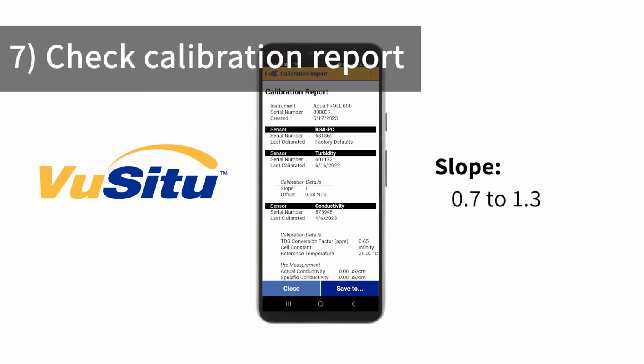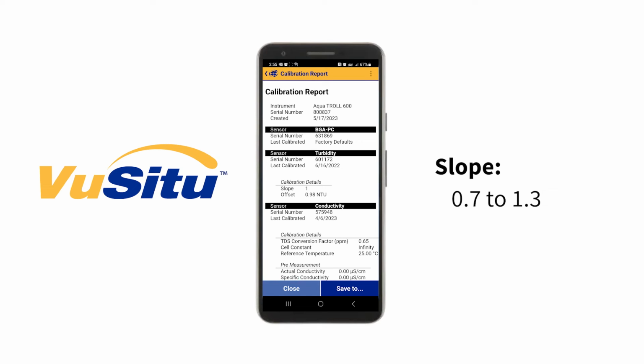If the slope is out of range, there's a few things you can try. First, clean the sensor, then try the calibration again. If the error persists, check for bubbles in the solution and ensure that the end of the restrictor is covered from ambient light. Verify that your calibration solution is not expired. Finally, you can restore calibration defaults under the Instrument Settings menu to return to the last factory calibration.